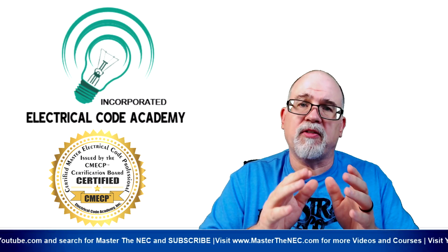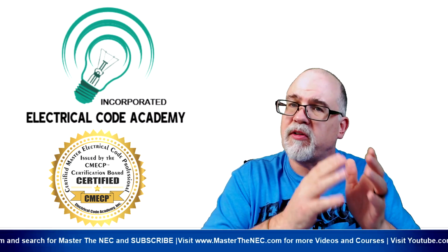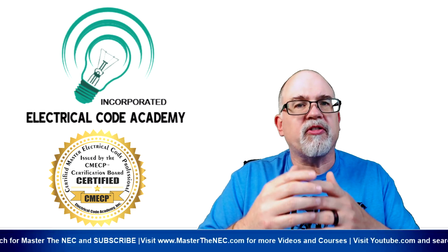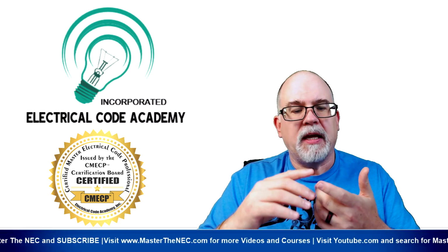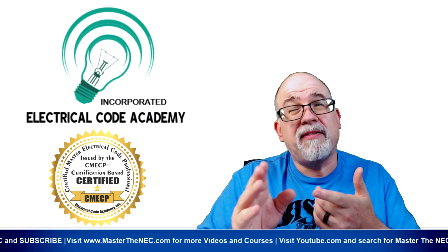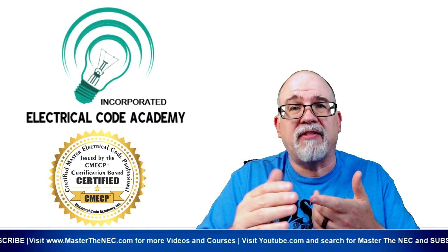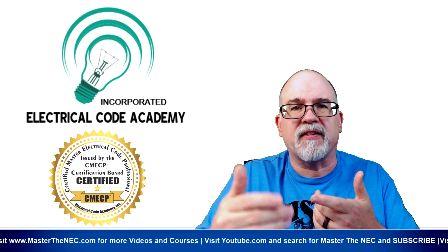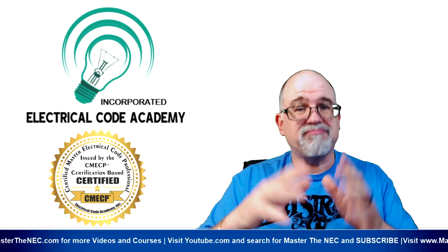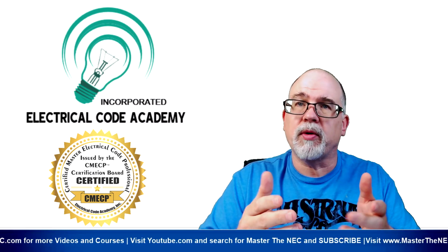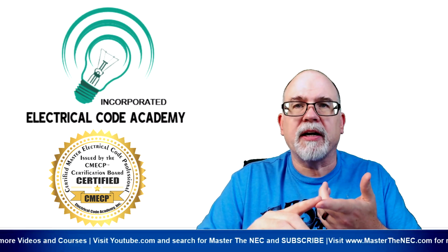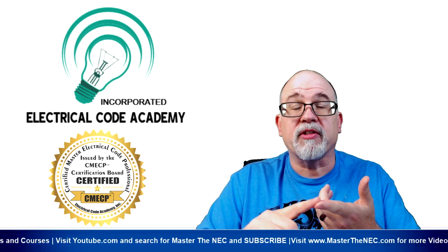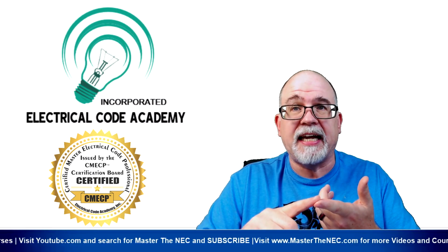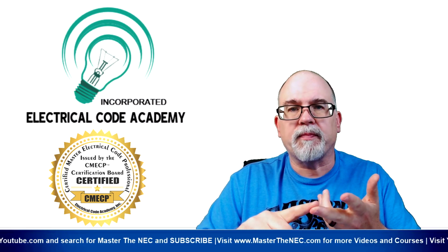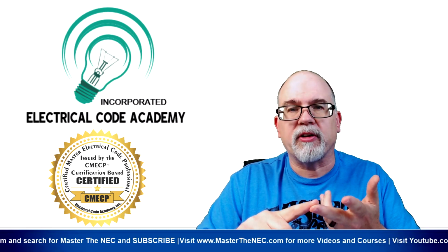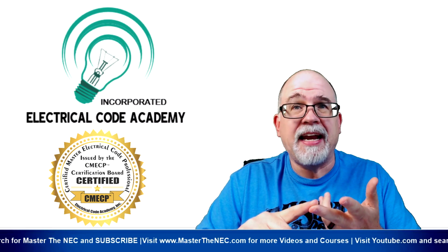Now, they're going to give you a couple givens here to kind of bring us up to speed. So assuming you watched part 1, 2, and 3, you understand that we're dealing with typically a 75 kVA transformer. Now, we're going to give you some examples today where it really doesn't matter the kVA because we're going to show you how to do multiple sizes for the secondary. But just to give you the lay of the land on what we've done to this point, we know that the primary current rating of a transformer of the 75 kVA is 90 amps. The secondary current rating of the transformer is 208 amps.